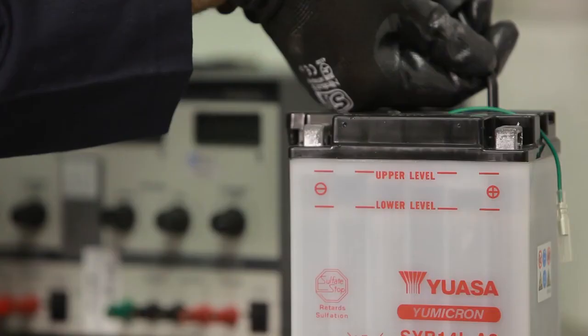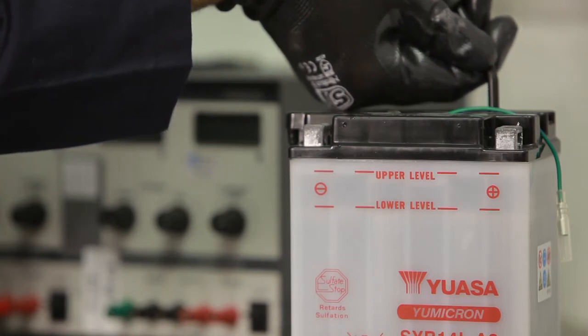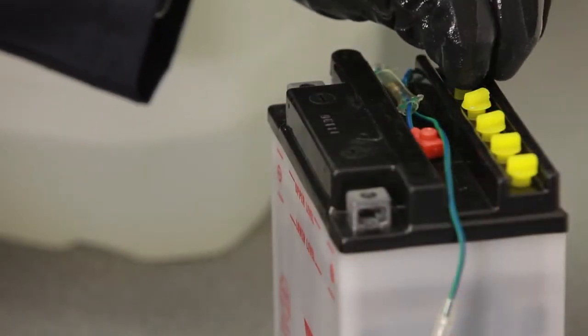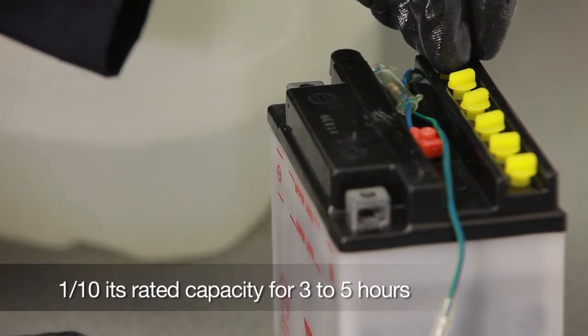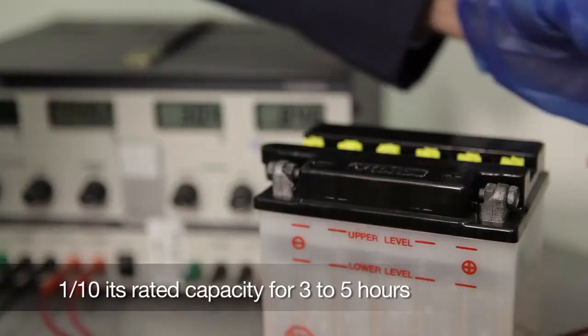If, after 30 minutes, the electrolyte level has fallen, top up to the upper fill level. Replace the filler caps loosely and begin to charge the battery at one-tenth its rated capacity for three to five hours. Charging at a higher rate could damage the battery.